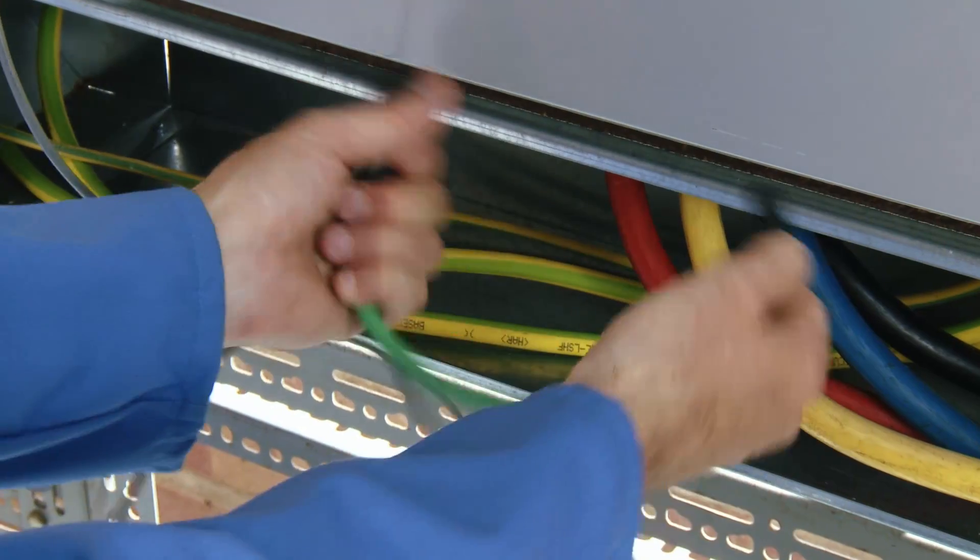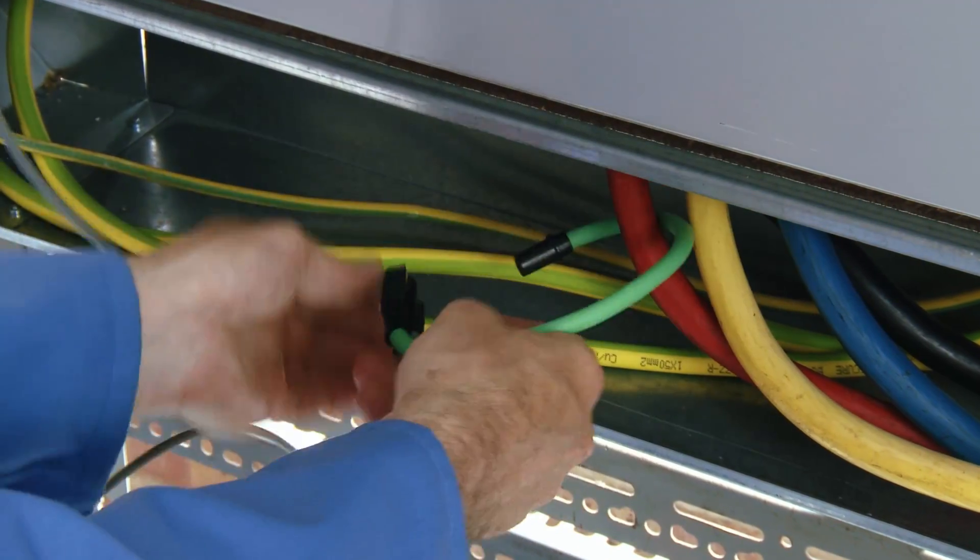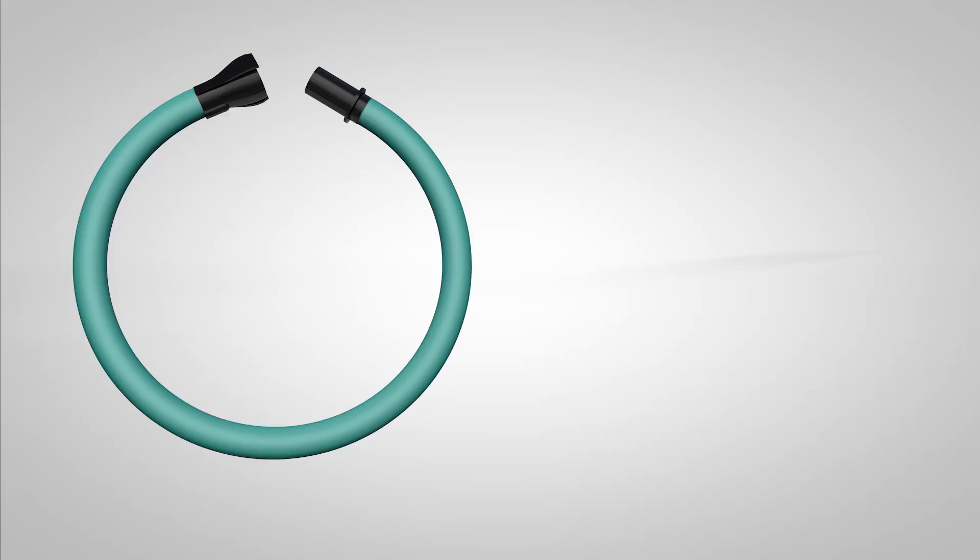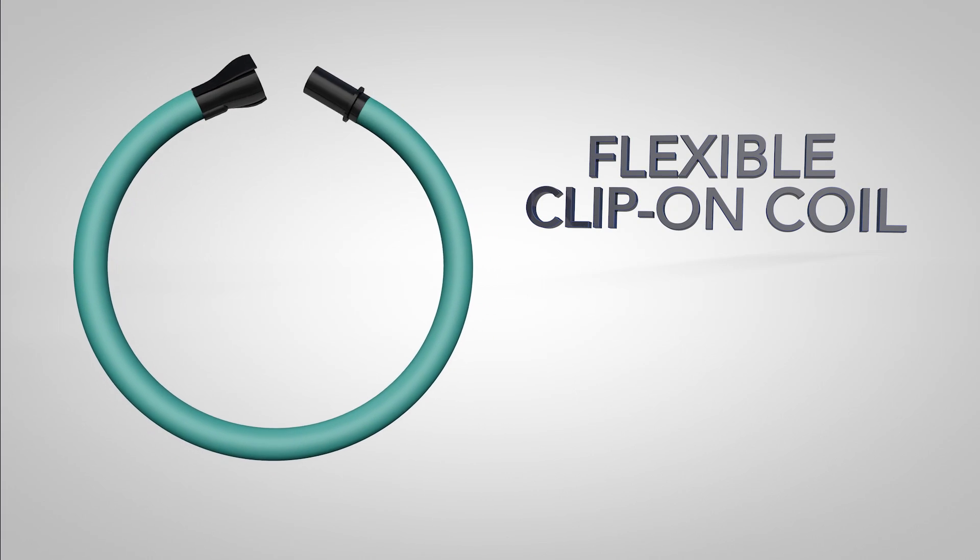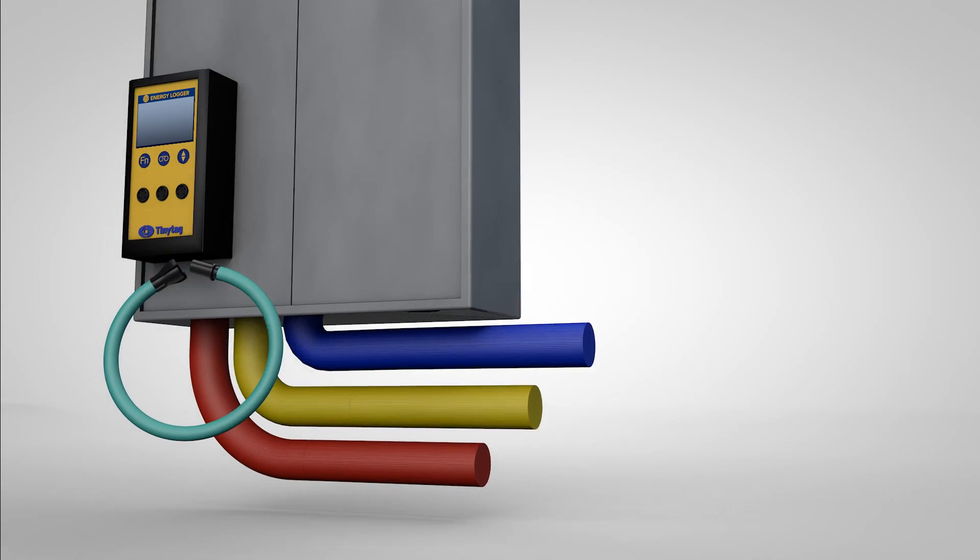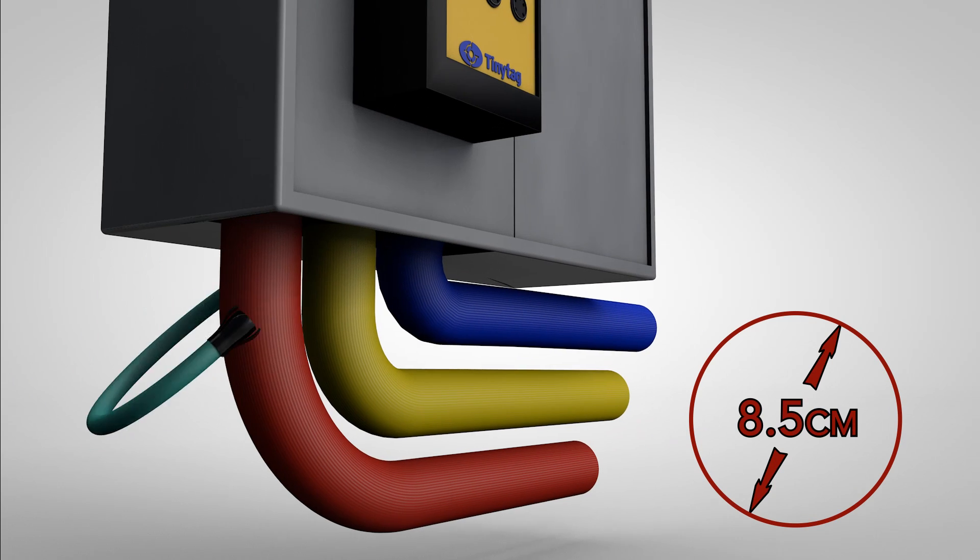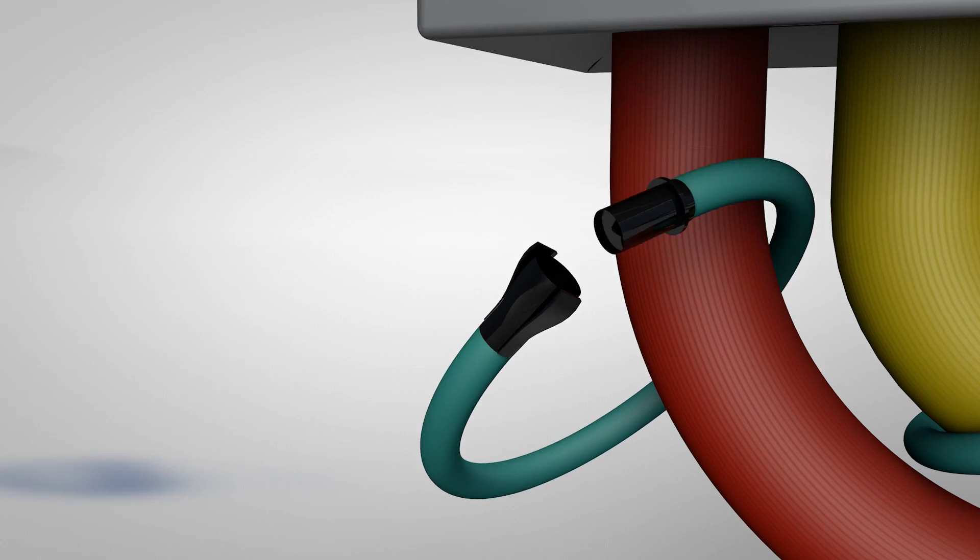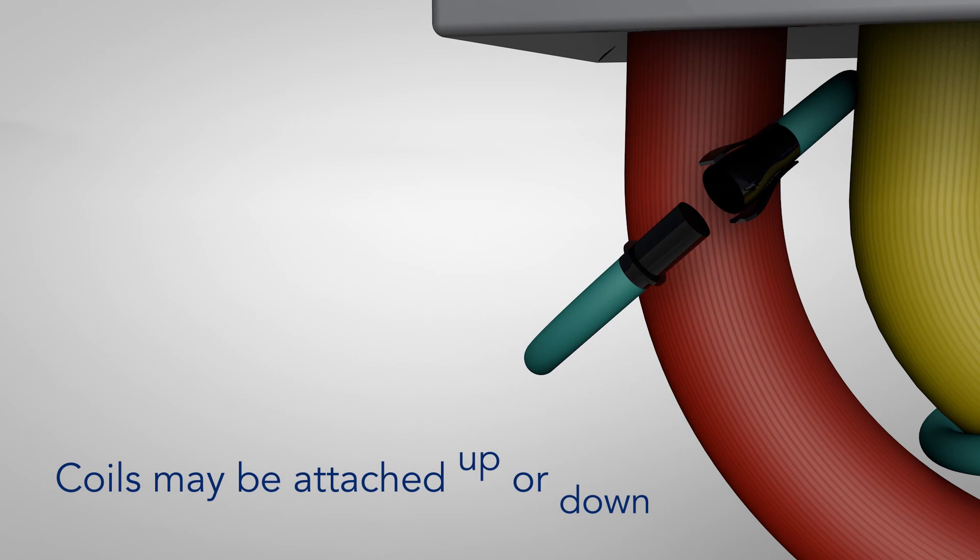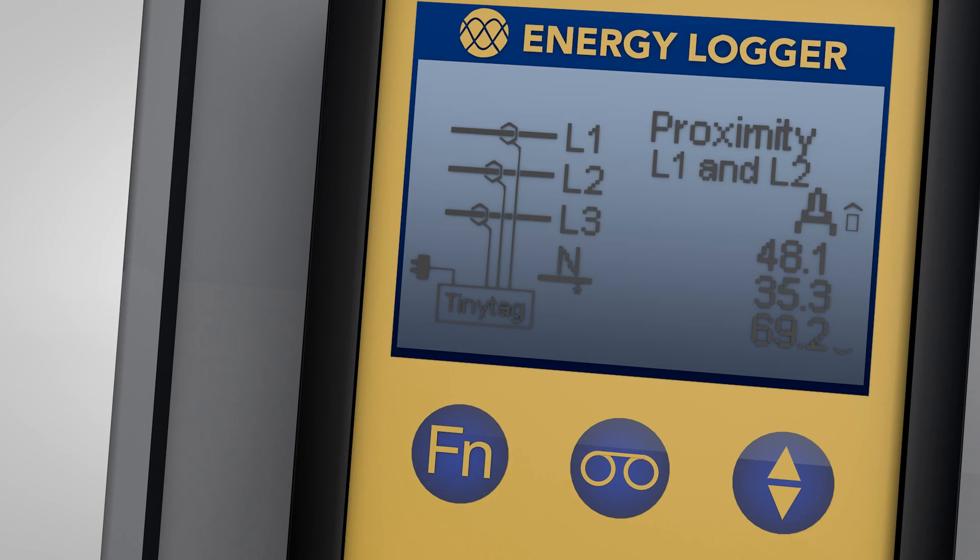Then connect the coils. These are flexible to allow easy positioning into small or awkward spaces. They are large enough to go around conductors of up to 8.5cm in diameter. The coils can be clipped around the cables either way up as the logger will automatically detect which way the current is flowing and adjust accordingly.